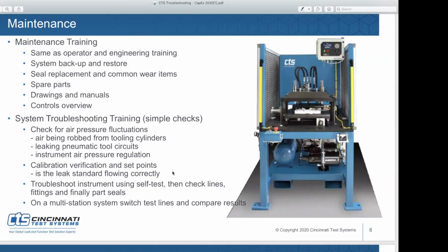So understanding what your spare parts are and where items are is always important too. Where are the O-rings? Where are the seals? What are the valves that you may have problems with? We suggest, for parts that may have debris in them, and you were talking about debris earlier and possible cutting fluids, putting an external exhaust valve close to the part. That way you're not exhausting all that debris up through your test line and through the instrument during an exhaust cycle. Yeah, that's something to keep in mind and mention.